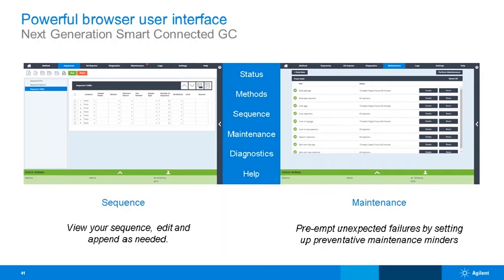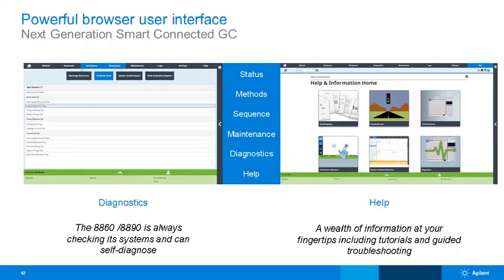And then maintenance on the right-hand side. This is really where, as I mentioned earlier, the GC will automatically start the timer should you do any maintenance through the system. By that I mean septa, liners, changing columns, a number of things. And as an experienced user in the lab, you'll know how many injections you can get down that system before any of those should be changed. And so what we have here is incorporated a maintenance timer, which will highlight to a more inexperienced user when, let's say, a liner should be changed, which will basically mean that it will change before you get a problem, which is what we're trying to achieve here: more uptime and less issues diagnosing what's gone wrong.